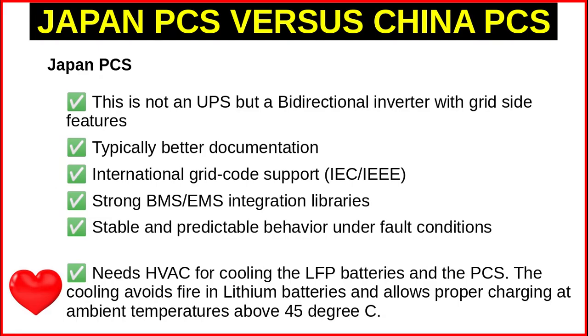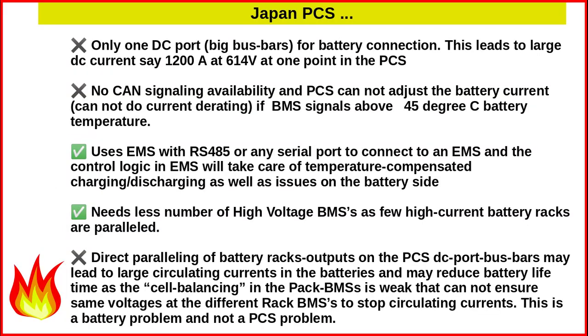And the last point, which is very good, is that it is mandatory to provide HVAC for cooling both the PCS and the LFP batteries. The cooling avoids fire in the lithium batteries and also allows proper charging at ambient temperatures above 45 degrees C. A particular feature of Japan PCS is that it has only one DC port for connecting to the batteries.